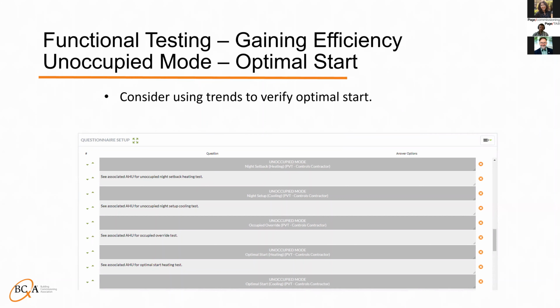Now, I don't know how many times I see morning warm up energize the AHU with a system of only fan power terminal units. You don't need the AHU for morning warm up if you have only fan power terminal boxes in your system. I also see the AHU energize in the occupied state during optimal start. Keep in mind, optimal start occurs before occupancy. You do not need outside air. So it's worth adding the comment in the design reviews to fully define optimal start to avoid a headache later. Like you can avoid the headache.